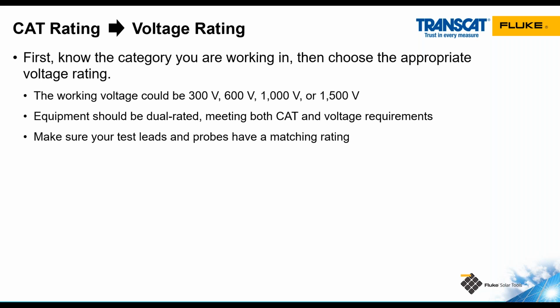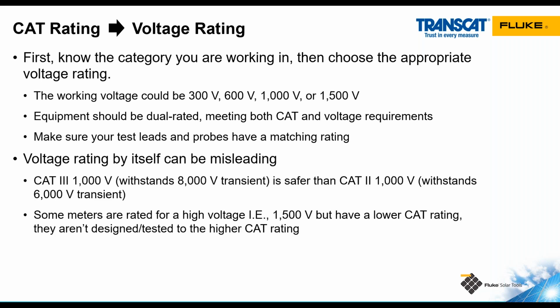You need to have the probes that are rated to match the meter that you're using. So if you're using, for example, the Fluke 393 clamp meter, which is a category 3 1500 volt meter, it comes with category 3 1500 volt test probes. But if those probes should become damaged and you need to replace them, category 3 1500 volt test probes are fairly uncommon. So it may be tempting to go into your toolbox and pull out whatever probes you have, but chances are they're not going to have that same category 3 1500 volt rating. And if you're working on a 1500 volt system, you may be introducing a point of failure into that test circuit.